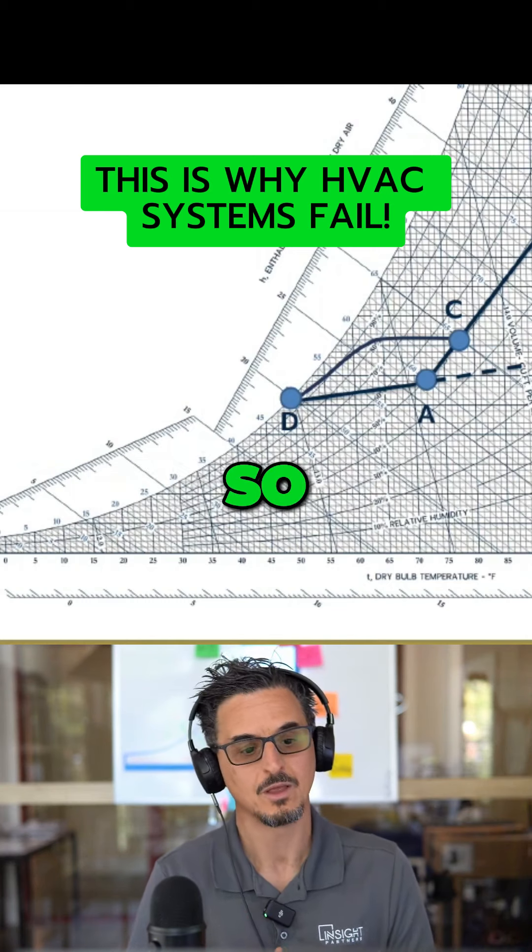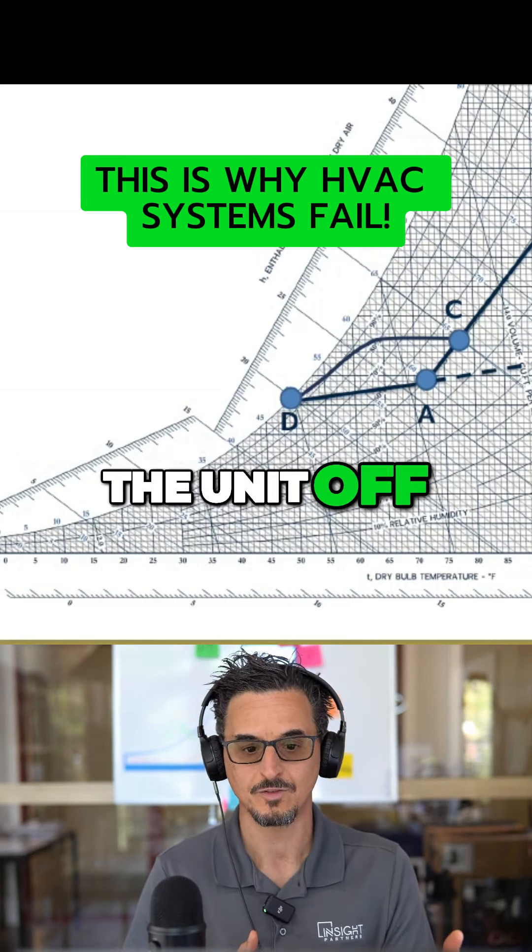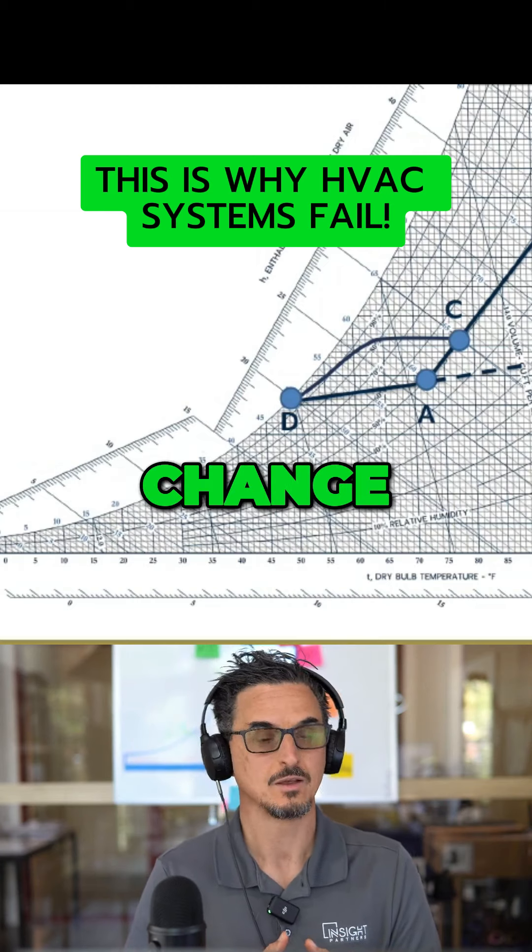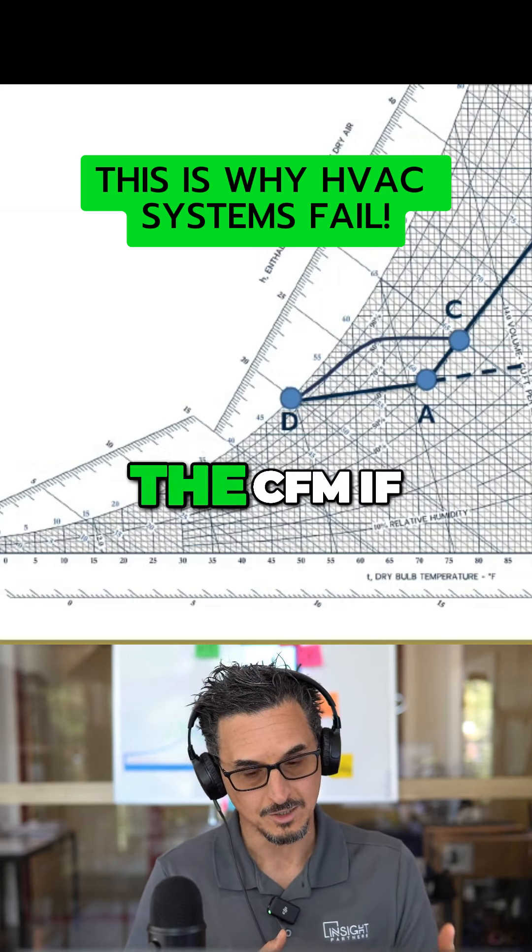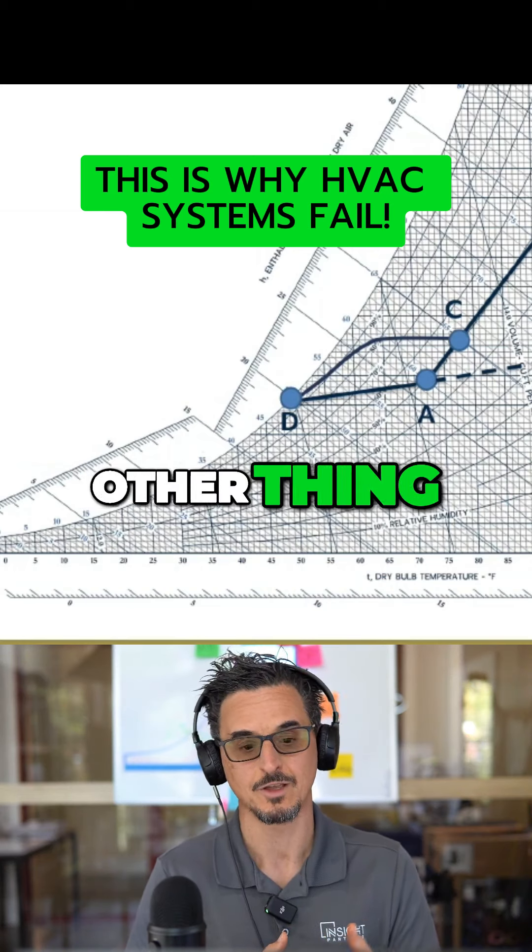So what are the options if it's a constant volume system? You can turn the unit off, which doesn't dehumidify very well. You can change the CFM if you have the ability to, if it's a constant volume unit.